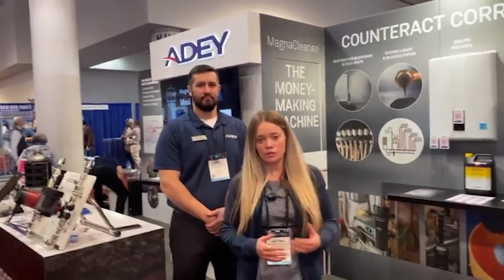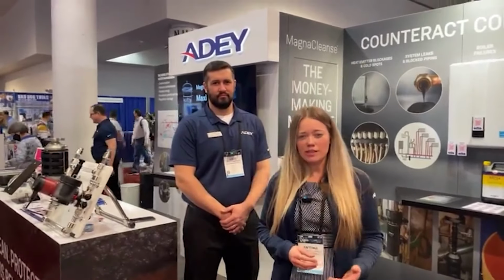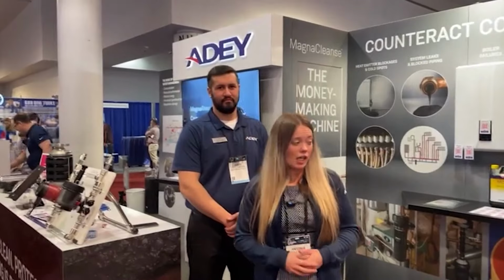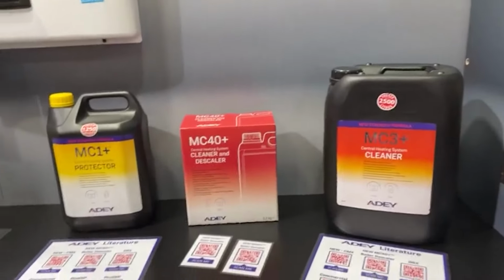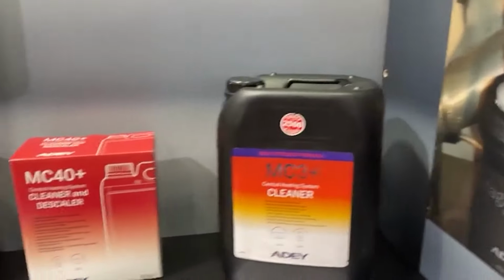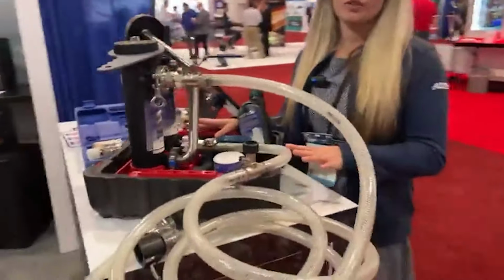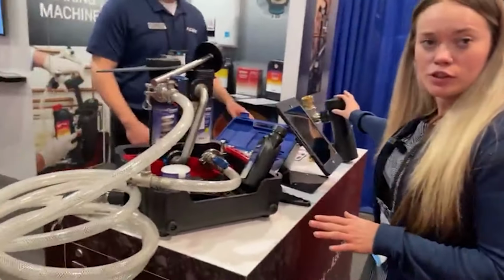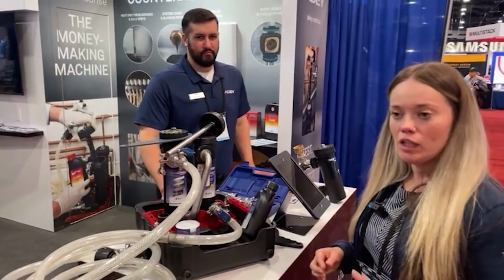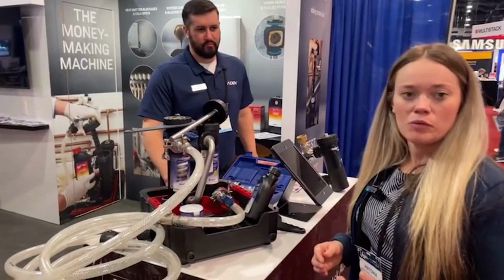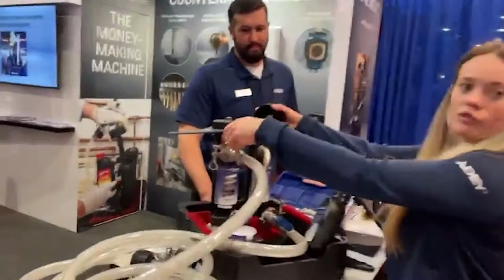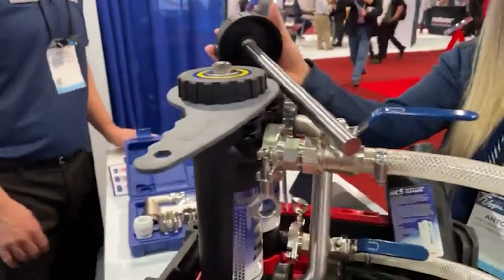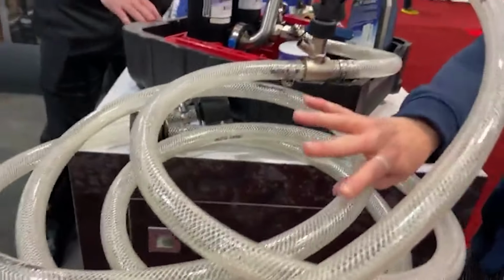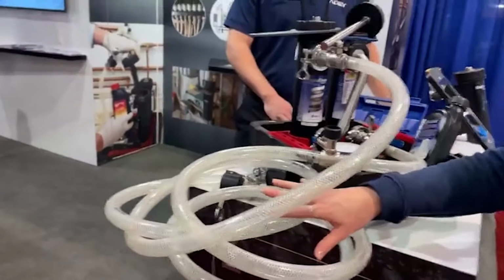So we've got a 3 simple step solution to preventing corrosion in new systems and counteracting it in retrofit systems. We've got cleaners that are designed to dislodge and lift magnetite and scale from system components, metal components, allowing them to be easily flushed out of the system. We then have this product here, which is the MagnaCleanse. This is designed to work with our magnetic filters, so you can hook it up to the valves and flush the system on a bypass sort of run. That means that you only have to drain the system once at the end, and all of the magnetite is captured on the magnet as the system is flushing the water through. You've got transparent hoses here, so you can actually see when the water is completely clean.